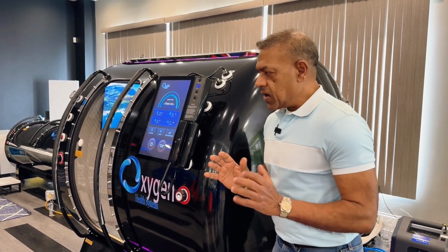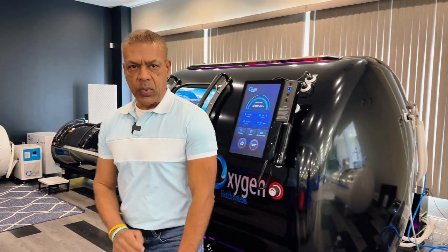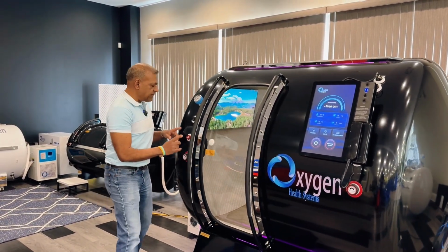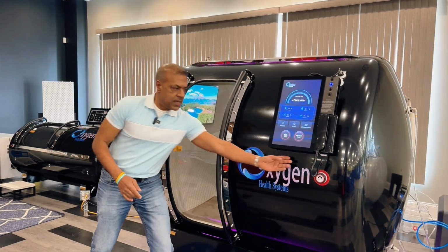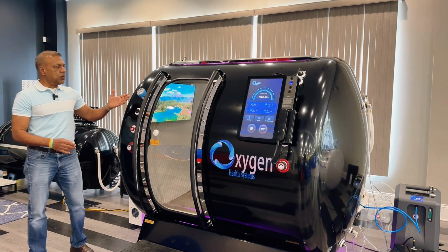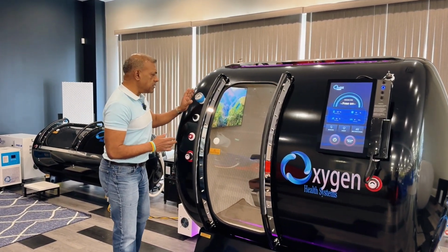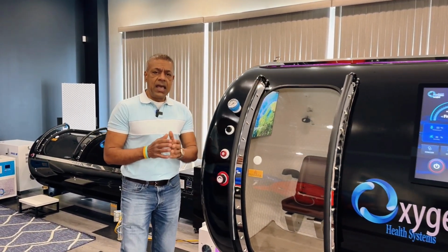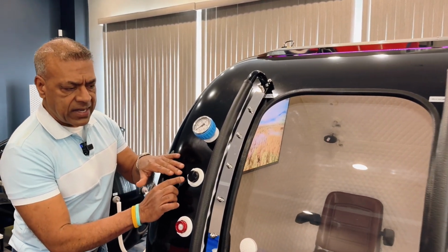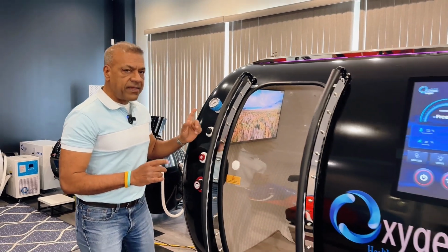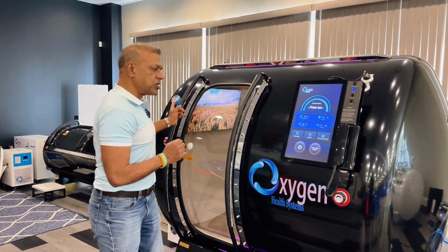not. So having said that, let's recap what we have for safety. We have open close valves, 2 of them. We have 2 emergency pressure release valves here. Next, we have the external pressure gauge, which is denoted in kilopascal, and at the same time, the internal pressure gauge, it would be installed right here inside. So whatever you can see from outside, you would be able to see the same pressure from inside. On top of that, we have a digital representation of that pressure here.